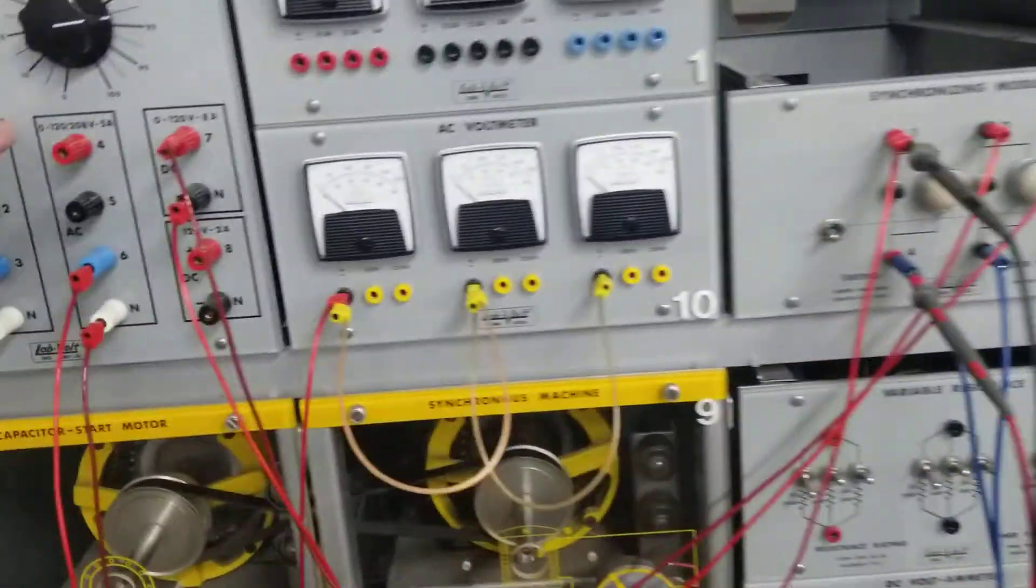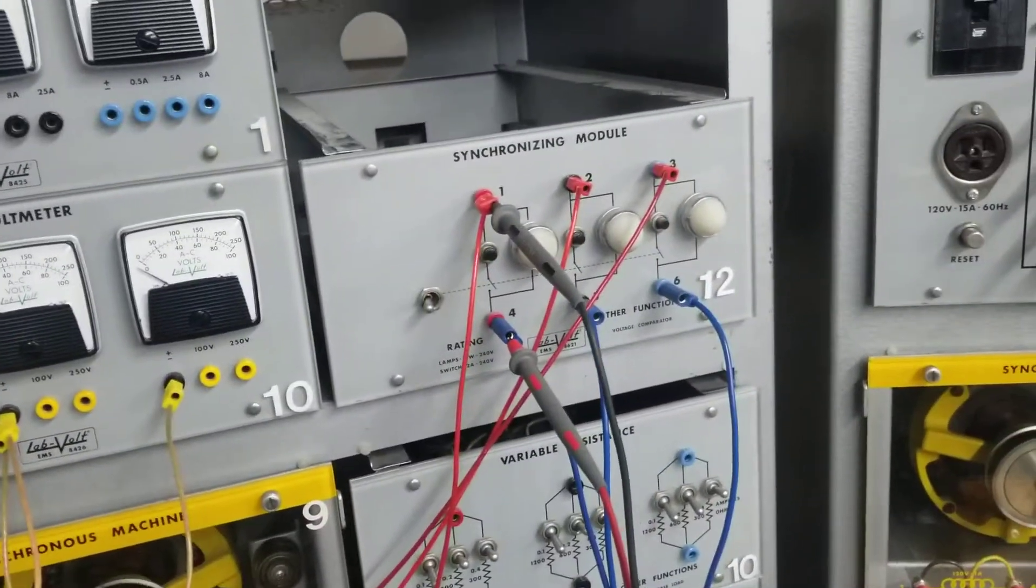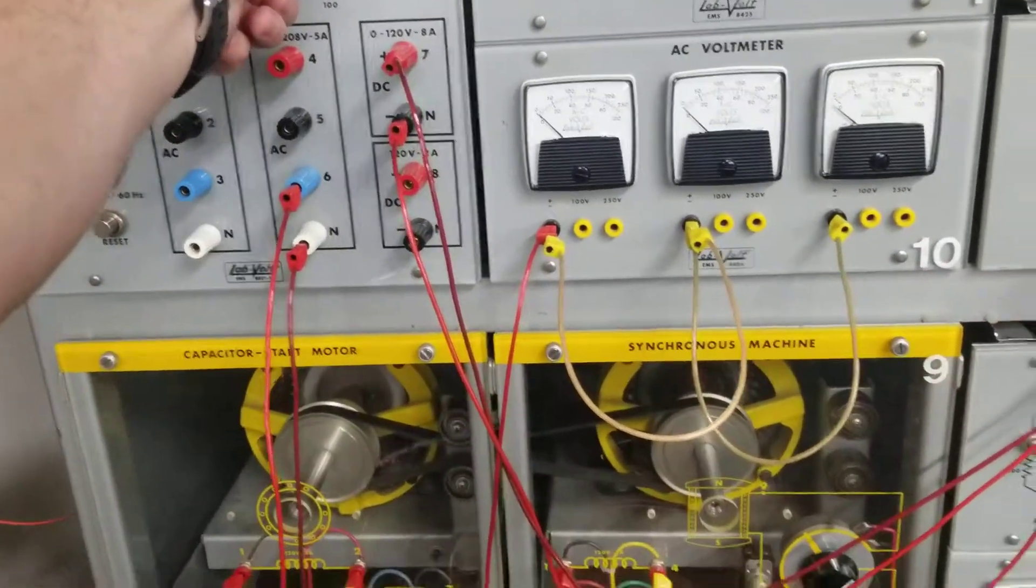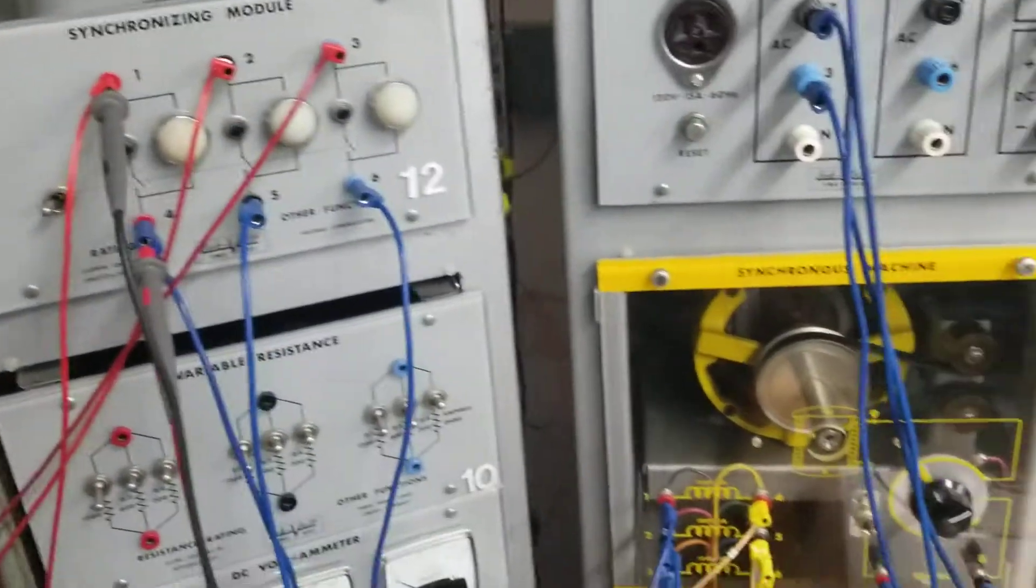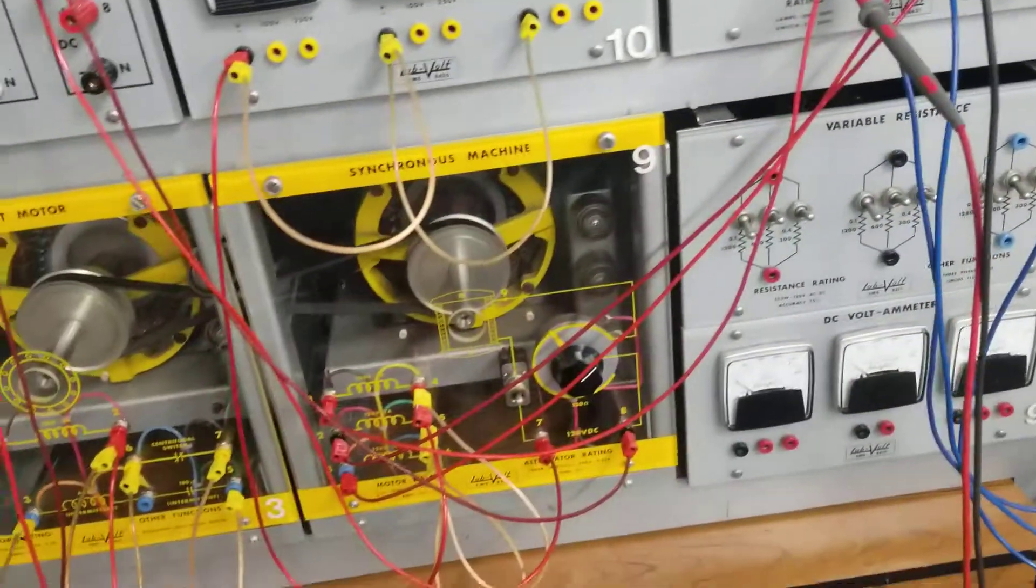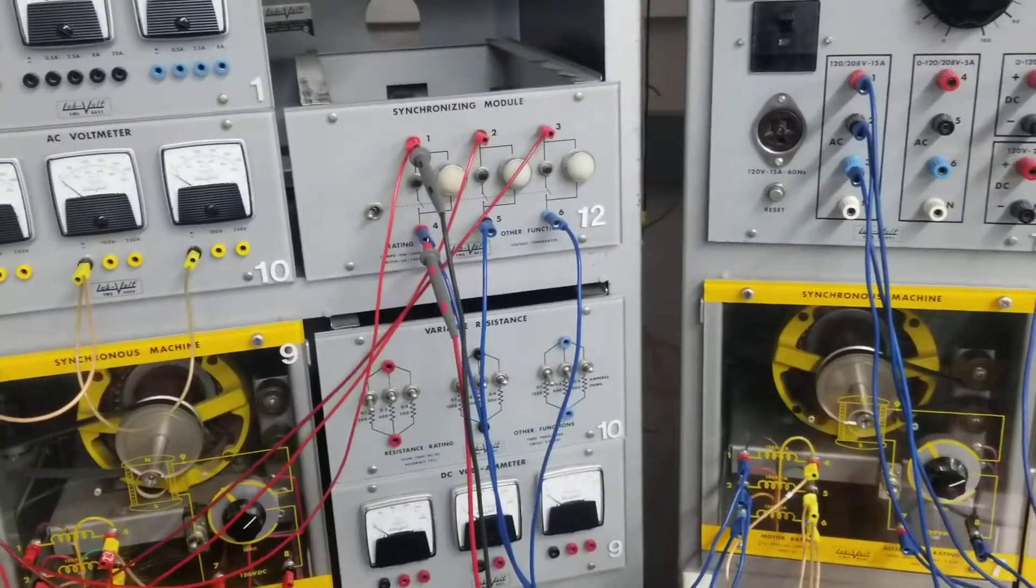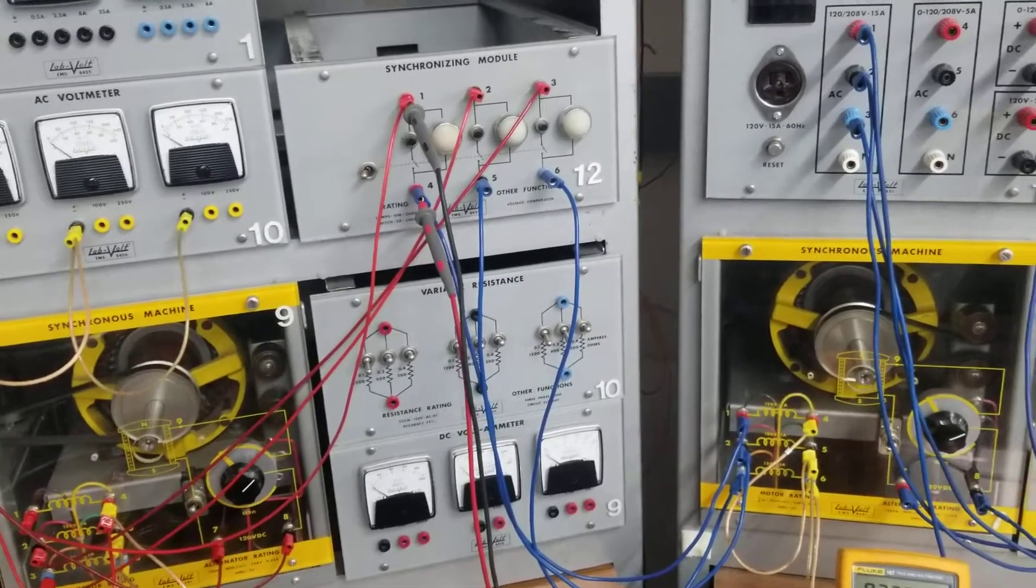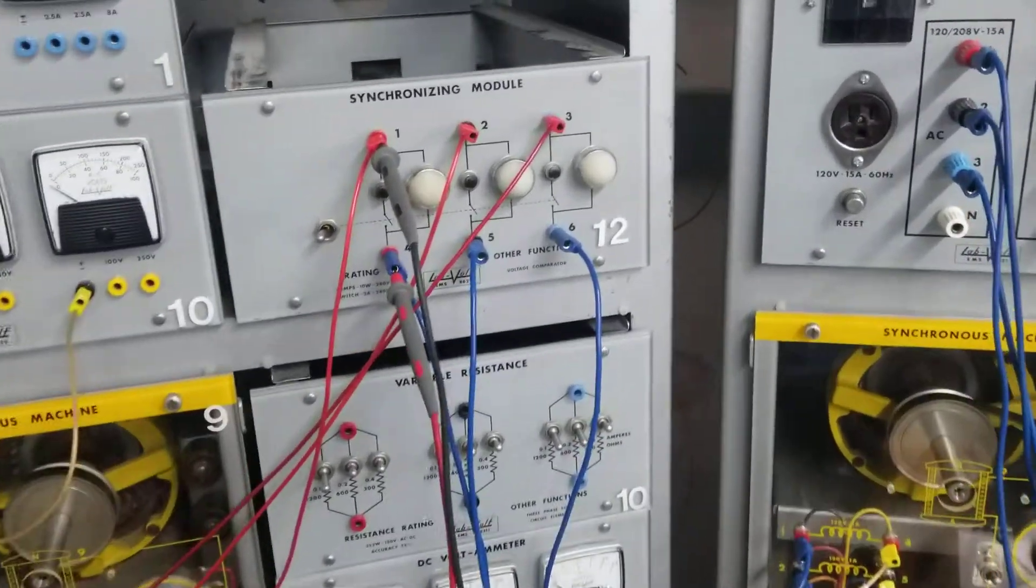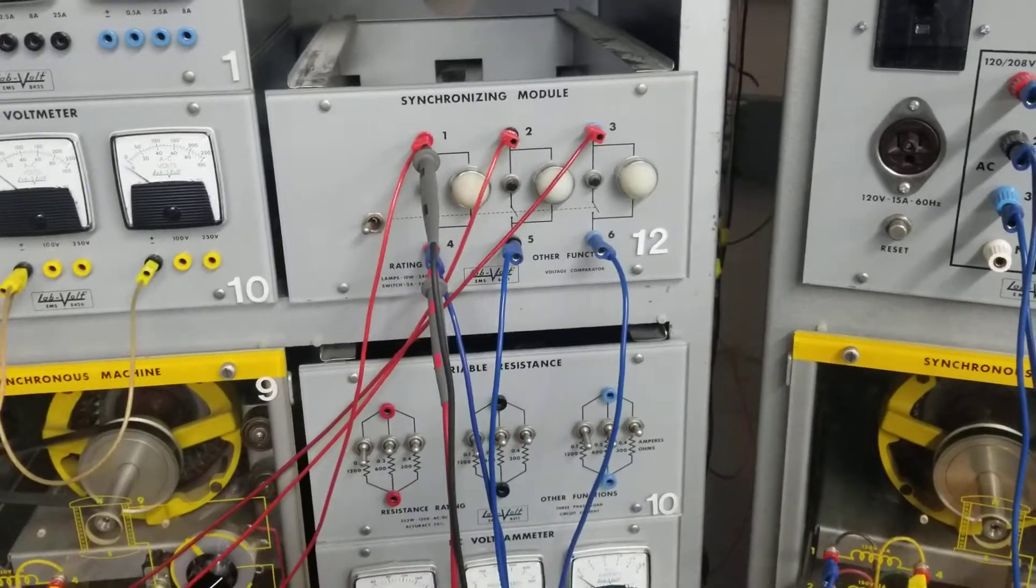If I decrease the speed on one of them, they're both locked together. I'm getting no difference in potential right now because essentially one generator is helping the other generator to bring it up to speed and treating it like a motor, like a load. But right now they're pretty much in sync. So that's why on the synchronizing module, you're getting no flashing.